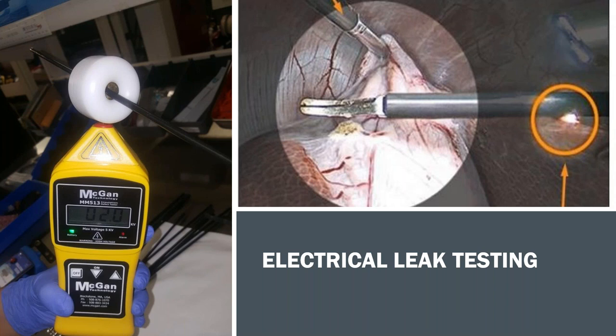So these electrical leak testers are another must-have for your quality management system. This should be done on every insulated instrument every time. A good idea would be to include a checkbox for this step in your documentation.